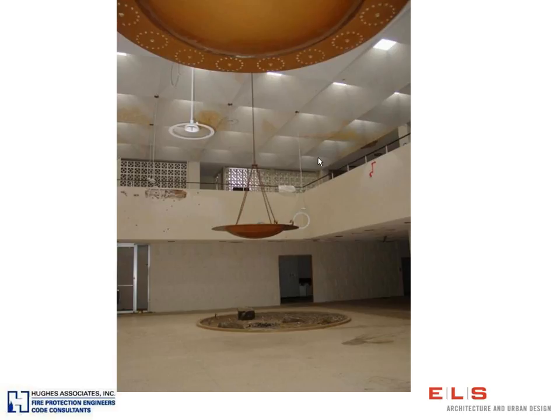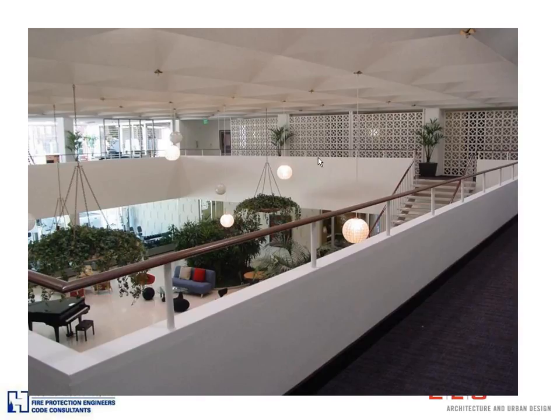And so what we ended up doing is to lay out every single sprinkler in this space, and it is in a non-symmetrical pattern. We laid it out to maximize coverage on the floor, to minimize obstruction by these planters, and to fit in with the aesthetic of the space. And so every sprinkler was laid out. We had a couple, literally 2 spaces, where we just were a few feet off on complete coverage, but that was accepted by the city of Pasadena. And as you can see, we ended up putting sprinklers here, right at the center point of these gussets.